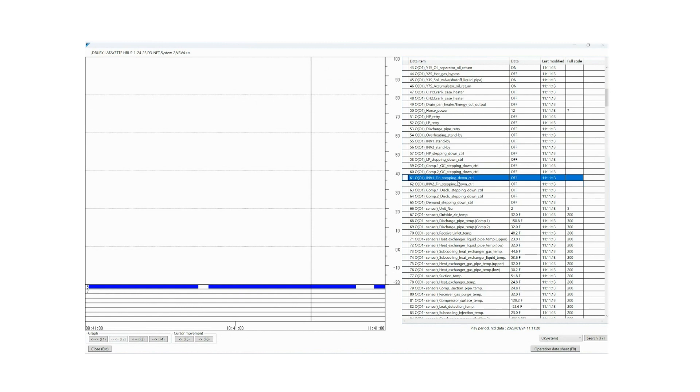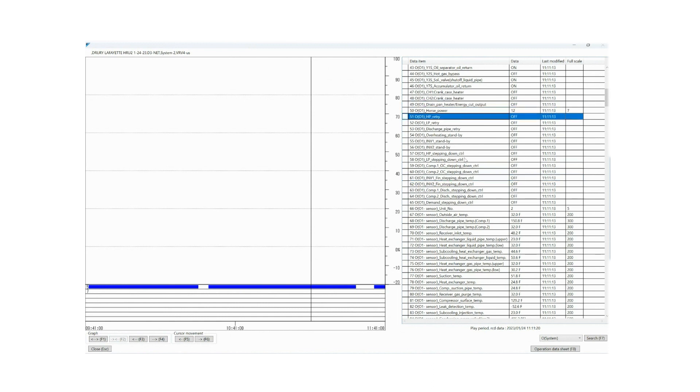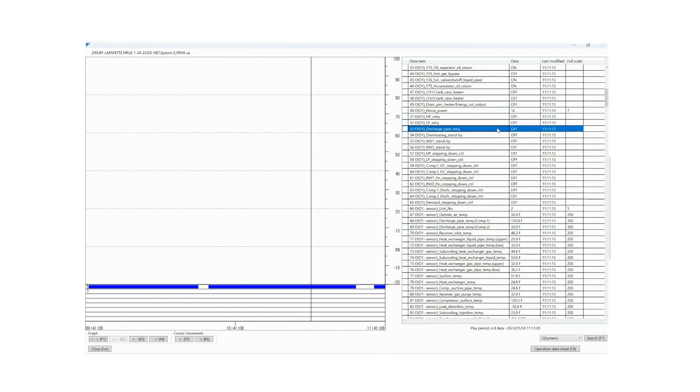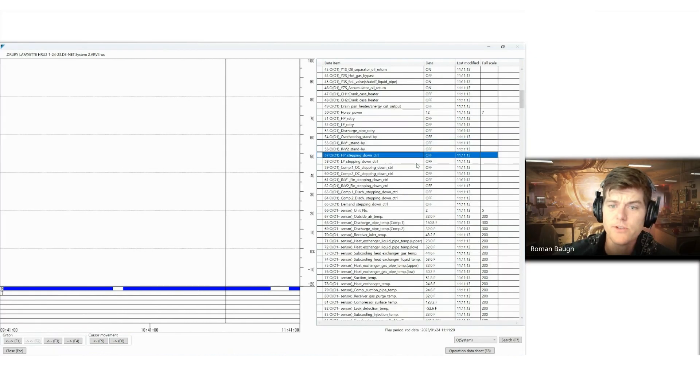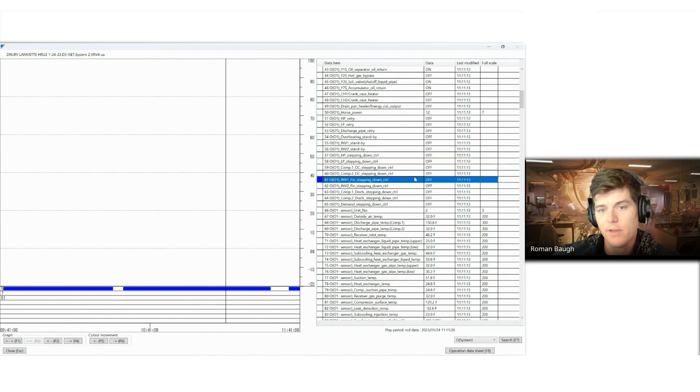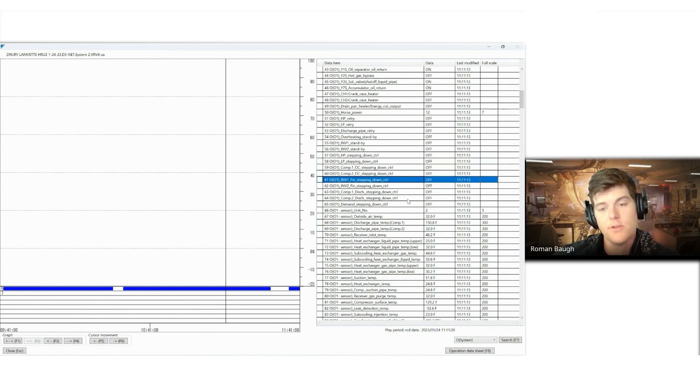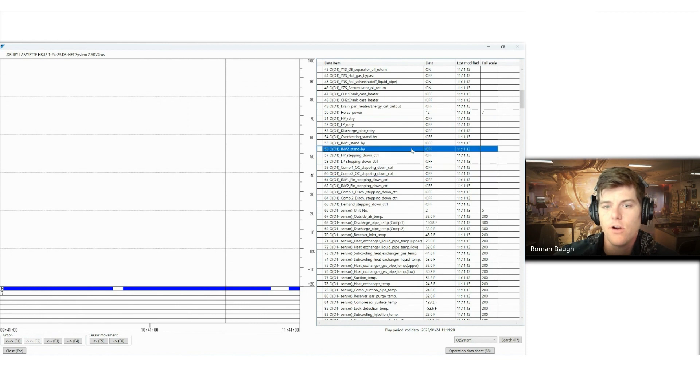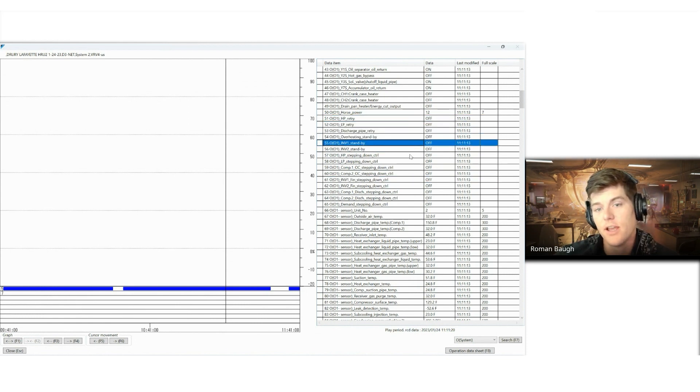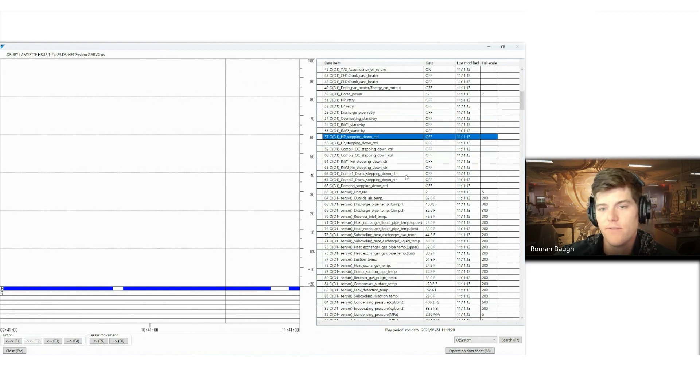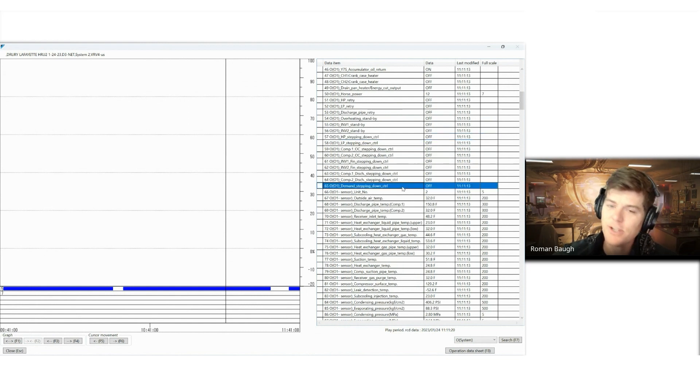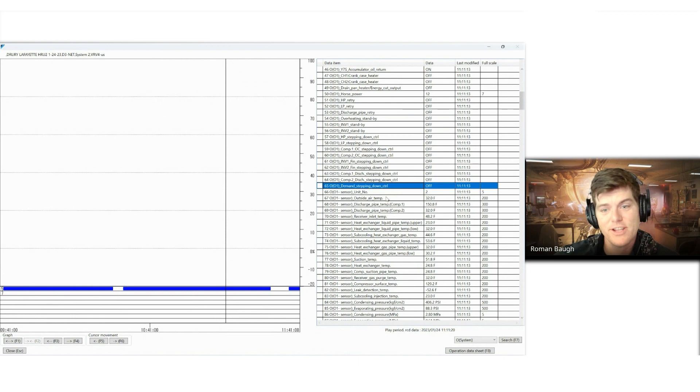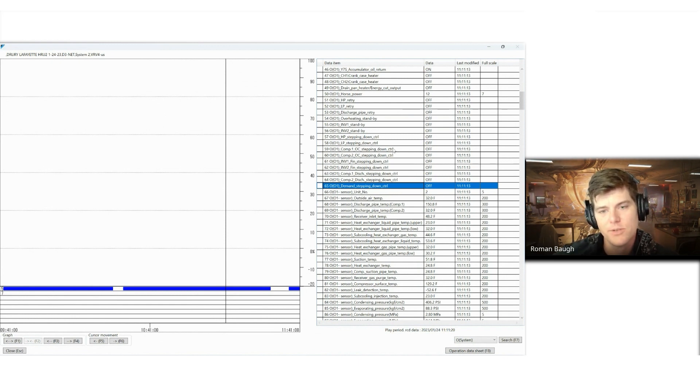All of these things are referenced in the service manual as to what their in and out conditions are. And so when I say in conditions, that means that whatever has to happen within the system data point for time, high temperature, low temperature, low pressure, high pressure, it will describe to you what has to happen for this to turn on, which is the in condition. And then it will also tell you what has to happen for it to turn off and let the system go back to normal control. If you ever see any one of these on from high pressure retry number 51 all the way down to number 69, there is an issue with your system or the system thinks there's an issue with your system. And if any one of these are on, you should be referencing your service manual to find out what has to happen for this to turn on. And then you go to your system and you start troubleshooting. These are dead giveaways as to an issue within the system. At any point in your data set, these get turned on, I would investigate. Doesn't mean that there's an issue. It just means that you should investigate further to find out if there is an issue, but it's designed to help you push you in the right direction as well as also protect the outdoor unit.